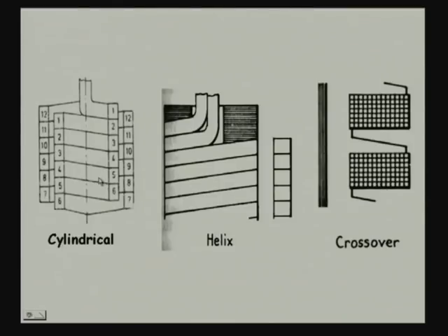This picture shows the diagram of different winding arrangement. The low voltage winding are usually made up of rectangular conductors, it may be a single conductor or a large number of strips taken together and wound on the insulating cylinder of the low voltage winding. Between turns, another set of duct and insulation will be provided on which a second layer can be wound.